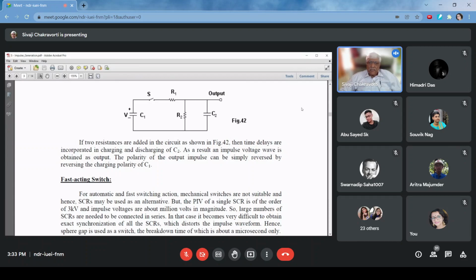But when you have a large number of SCRs in series and when the SCRs get turned on, you all know that there is a turn on time of SCRs, which is well defined by the manufacturers, but still there will be some difference from SCR1 to SCR2 to SCR3, etc. And it is extremely difficult to exactly synchronize the turning on of all the SCRs. So that creates quite a problem and distorts the wave front. So what to do? What is the solution?